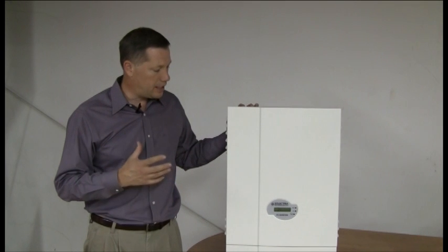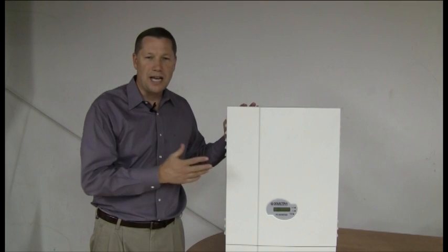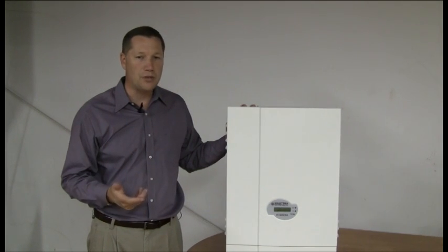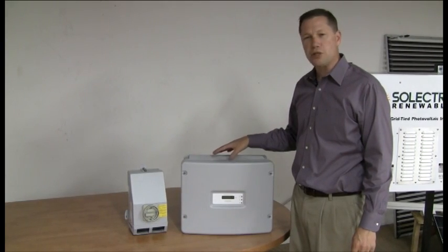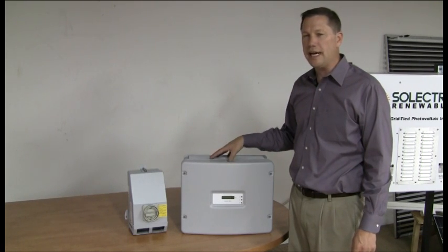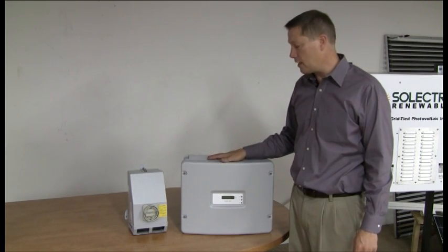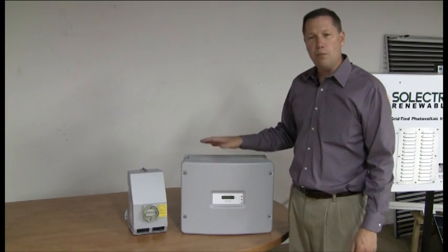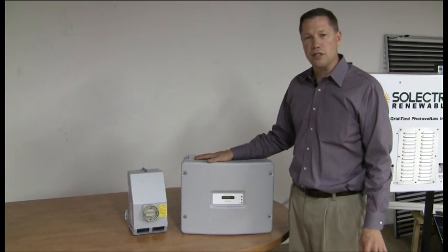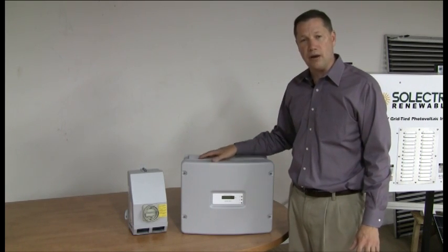Solectria is an example of a high-frequency inverter. It has a thin profile, about the size of a typical panel board that you might find in a house or in a commercial installation. SMA inverters are the most common inverters in North America, and they use a standard transformer in lieu of a high-frequency transformer like the Solectria. This makes them a little heavier and they stick out a little further from the wall, but most of these inverters can be installed inside or outside, as they're rated for use in the rain.